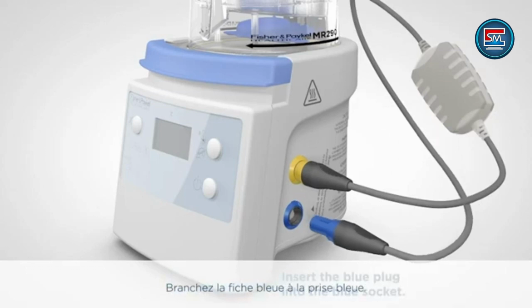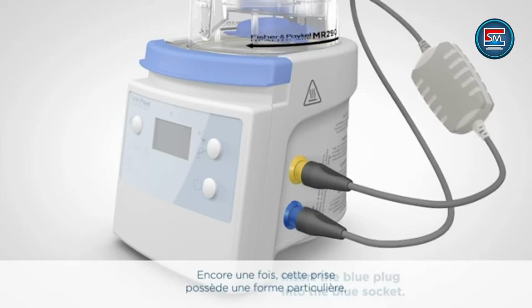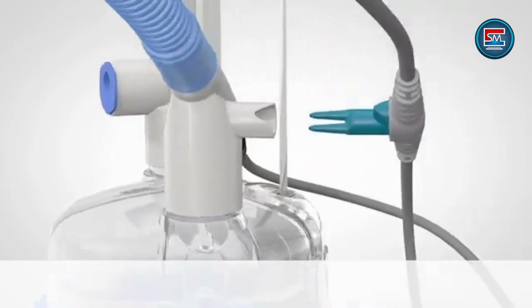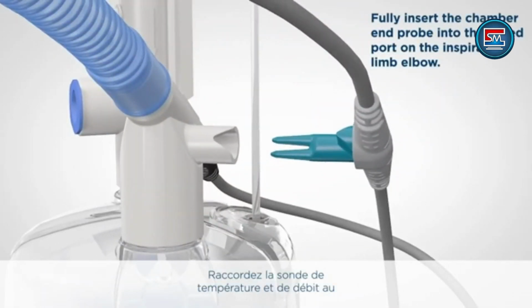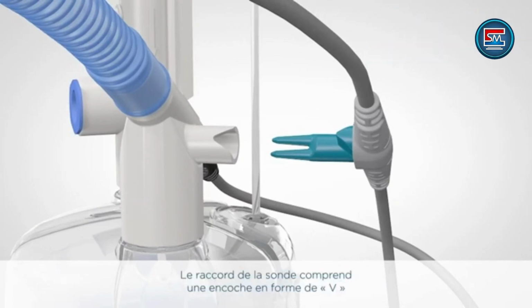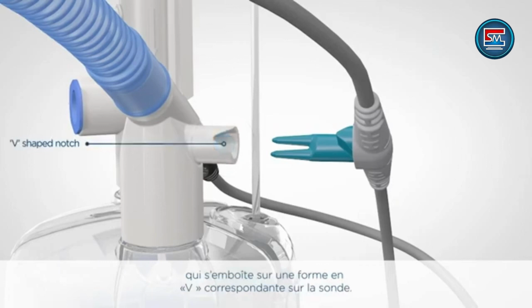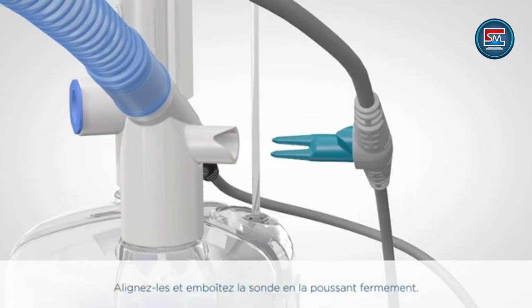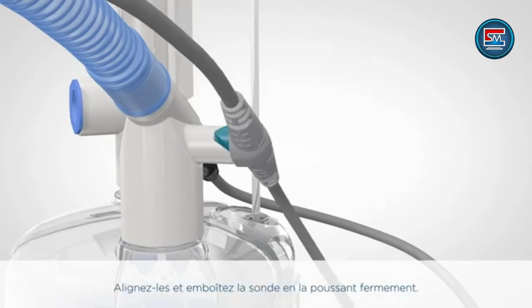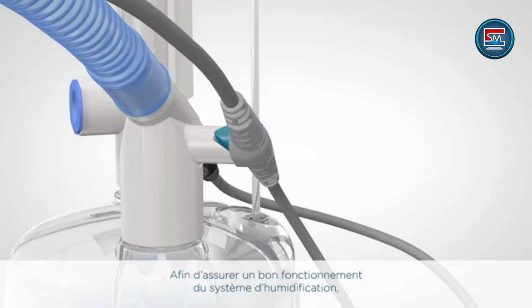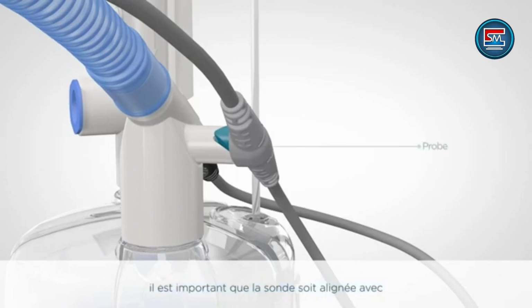Connect the blue plug to the blue socket. Again, this socket is keyed, so you may have to turn the plug to insert it. Again, it should click into place. Connect the temperature and flow probe to the port in the side of the elbow connector. The probe port includes a V-shaped notch corresponding to a V-shape on the probe. Line these up and push the probe firmly into place. Infant circuits use a friction fit. It is important for correct operation of the humidification system that the probe is lined up with the V-notch and inserted fully.